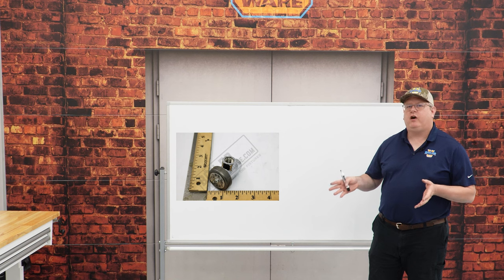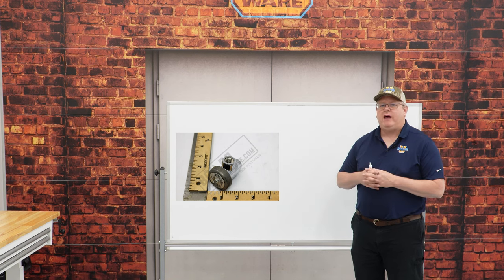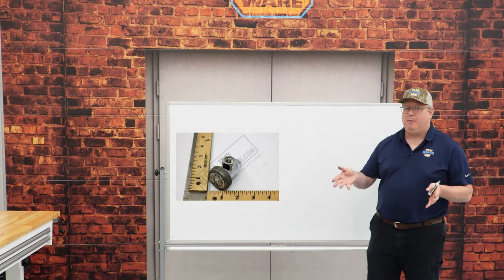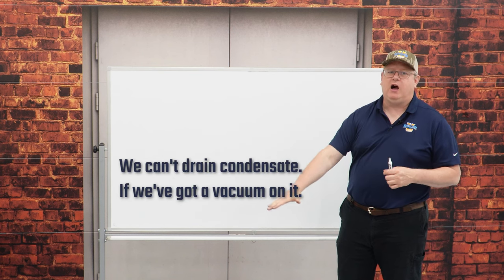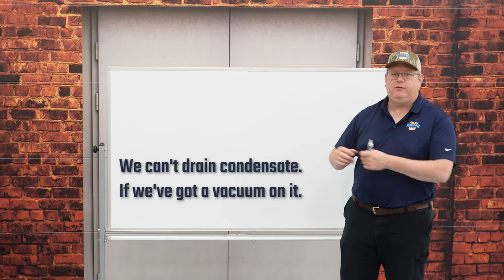On this week's boiler tip, we're going to talk about vacuum breakers. Vacuum breakers have a really important job because when we shut a piece of equipment down, a heat exchanger or a boiler, we don't want a vacuum to form on that exchanger. One reason is on a process heat exchanger, we can't drain condensate if we've got a vacuum on it.